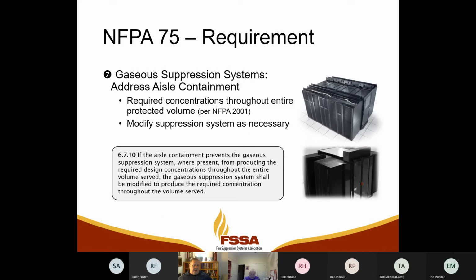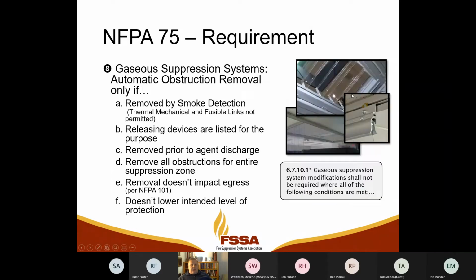Now, there are products that are meant to do this. I'll go back a slide here. This is a cold aisle containment system roof, and it's like a roll down shade. You remember those roll down shades that come down out of a roll and cover a window? Well, this is the same thing, but horizontally. There'll be a releasing device at the end. It can be tied into the fire alarm system. It'll activate release, and this thing will, via a spring, just roll up into this box at the end and open everything up. Systems like this, and maybe on this next page, can have louvers that automatically spring open once released. There's a number of ways to get gas in there without modifying the system.